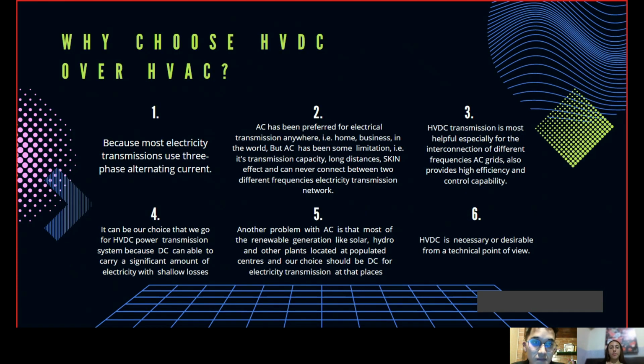And why choose HVDC over HVAC? HVDC transmission is most helpful, especially for the interconnecting of different frequencies. AC grids also provide high efficiency and control capacity. It can be our choice that we go for an HVDC power transmission system because DC can carry a significant amount of electricity with fewer losses. Another problem with AC is that most of the renewable generation, like solar, hydro, and other plants, are located away from populated centers, and our choice should be DC for electricity transmission at those places. HVDC is necessary or desirable from a technical point of view.